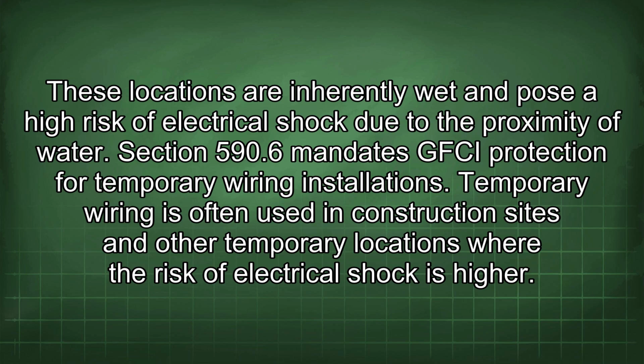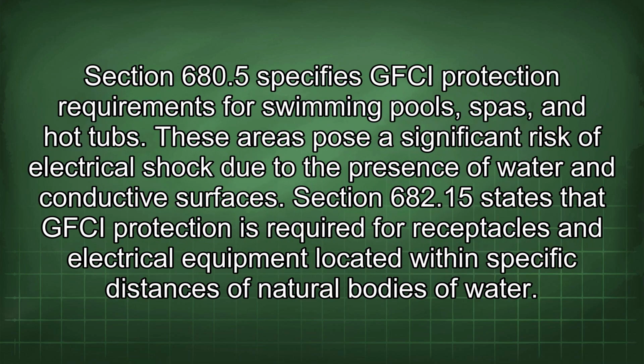Section 590.6 mandates GFCI protection for temporary wiring installations. Temporary wiring is often used in construction sites and other temporary locations where the risk of electrical shock is higher. Section 680.5 specifies GFCI protection requirements for swimming pools, spas, and hot tubs. These areas pose a significant risk of electrical shock due to the presence of water and conductive surfaces.